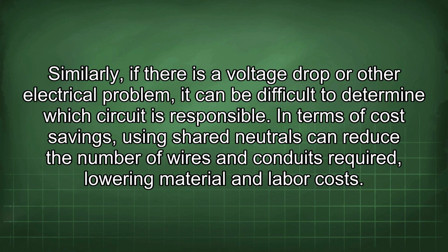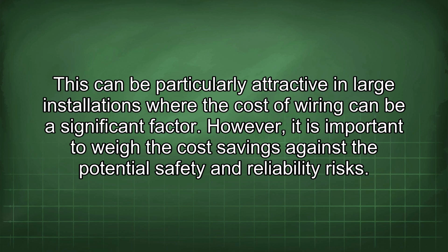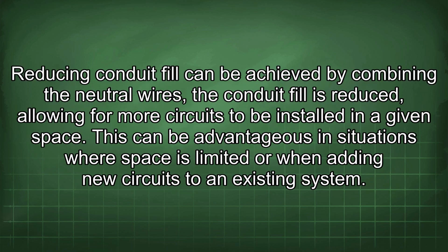In terms of cost savings, using shared neutrals can reduce the number of wires and conduits required, lowering material and labor costs. This can be particularly attractive in large installations where the cost of wiring can be a significant factor. However, it is important to weigh the cost savings against the potential safety and reliability risks. Reducing conduit fill can be achieved by combining the neutral wires. The conduit fill is reduced, allowing for more circuits to be installed in a given space. This can be advantageous in situations where space is limited or when adding new circuits to an existing system.